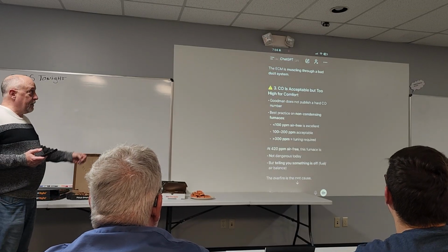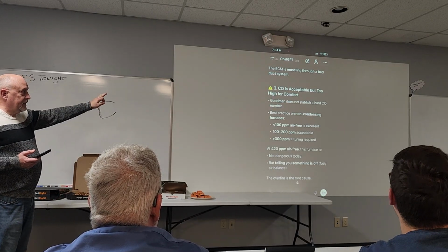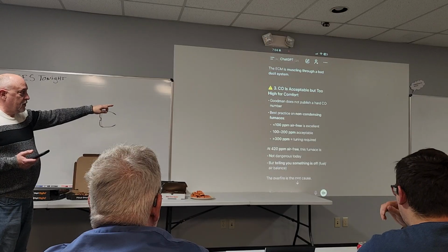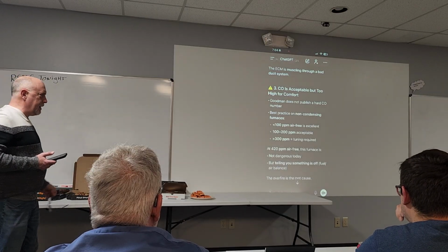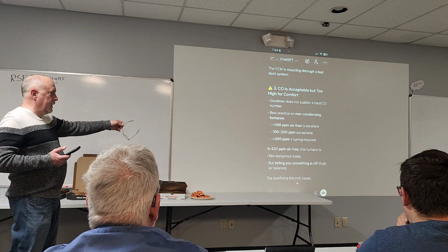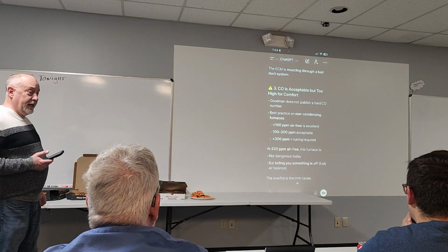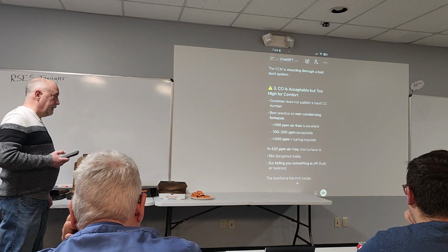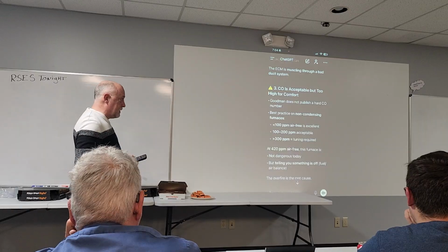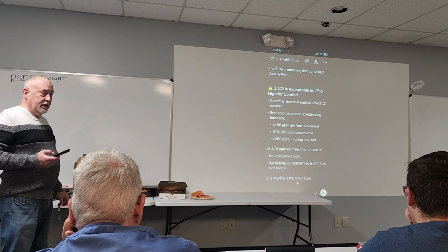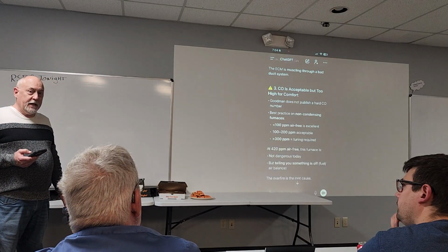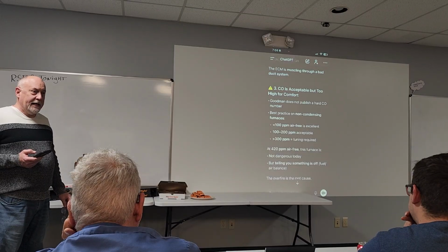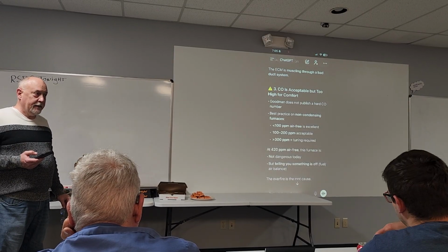No, but think about what this says right here. It's saying above 300 ppm tuning is required, and at 400 air free, the furnace is not dangerous today. Well, that's not right. It's telling you something's off with the fuel-air balance. But this is the primary reason we don't want to rely on AI to make safety decisions.